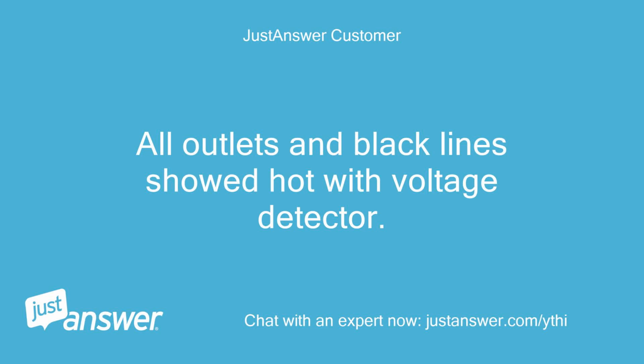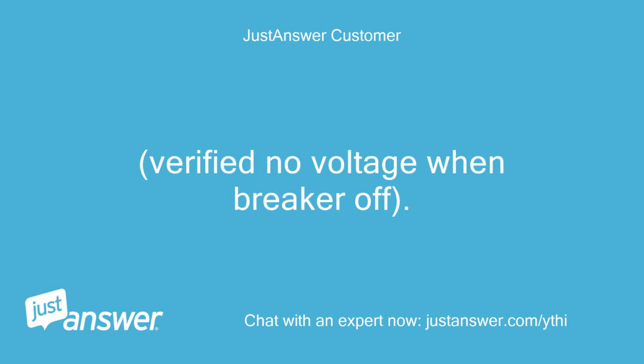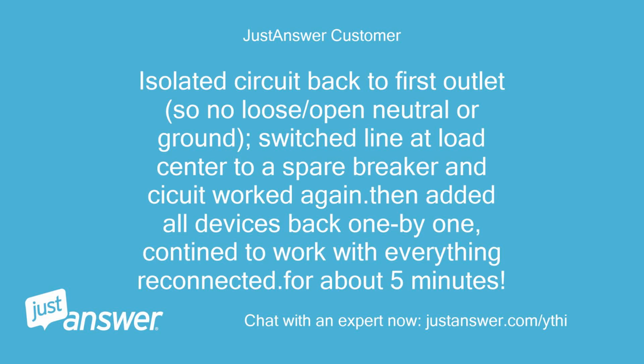All outlets and black lines showed hot with a voltage detector. I verified no voltage when the breaker was off. I isolated the circuit back to the first outlet, so no loose or open neutral or ground. I switched the line at the load center to a spare breaker and the circuit worked again. Then I added all devices back one by one, and it continued to work with everything reconnected for about 5 minutes.